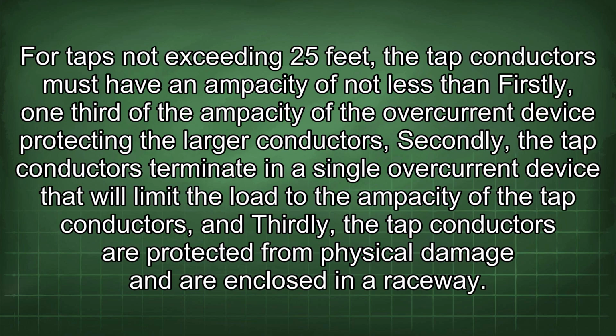For taps not exceeding 25 feet, the tap conductors must have an ampacity of not less than, firstly, 1/3 of the ampacity of the overcurrent device protecting the larger conductors. Secondly, the tap conductors terminate in a single overcurrent device that will limit the load to the ampacity of the tap conductors. And thirdly, the tap conductors are protected from physical damage and are enclosed in their raceway.